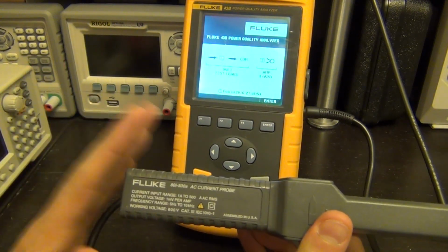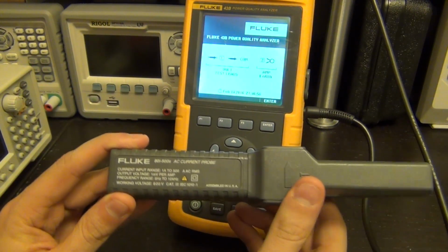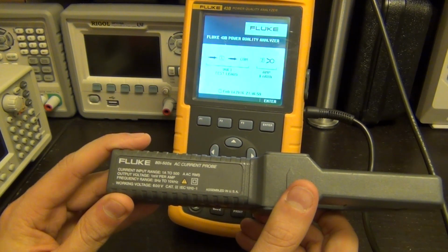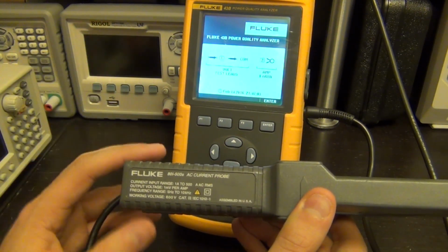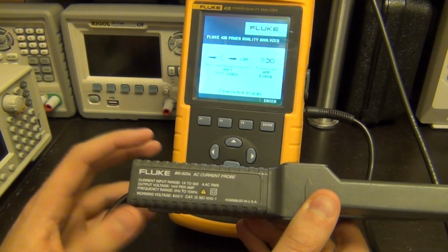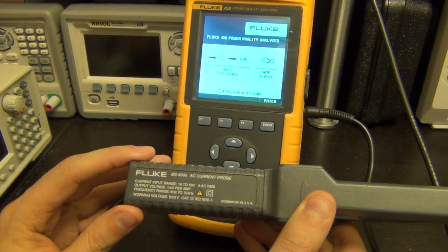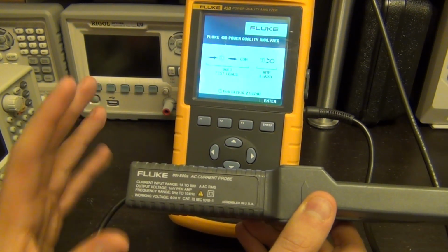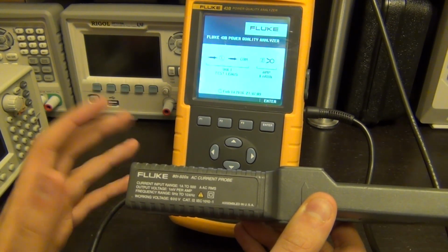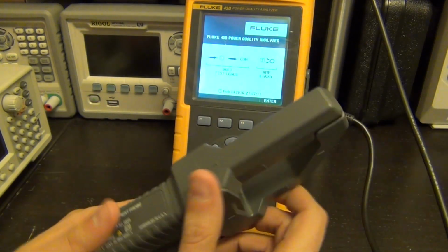So this is a very high current unit, obviously intended for industrial application or even measuring current coming into your house and leaving it on somewhere where you can do long-term capturing of data. This indeed is a 1 millivolt per amp pickup, and it works all the way from 5 Hertz to 10 kilohertz. Obviously, it has to be AC because of the principle of operation.